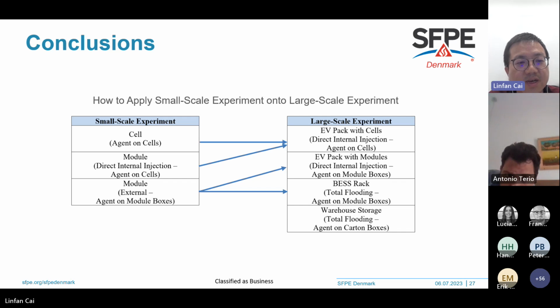For instance, in the cell level experiment where agents are discharged directly onto the cells, this is similar to the EV pack level with battery cells housed within it, using the direct internal injection method. For the module level experiment, the direct internal injection method can also be applied to the EV pack level with modules. Then for the module level experiment with external spray, this can be applied to the EV pack level with modules, and also to battery energy storage system rack levels, because the way the modules and cells come into contact with the agents is quite similar.